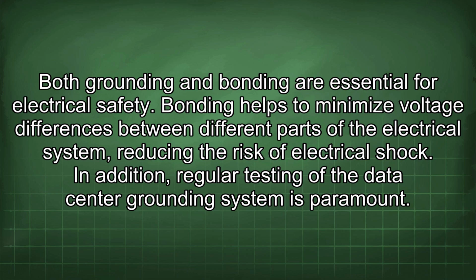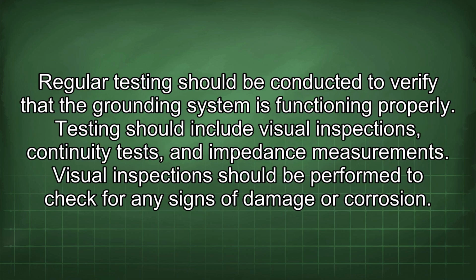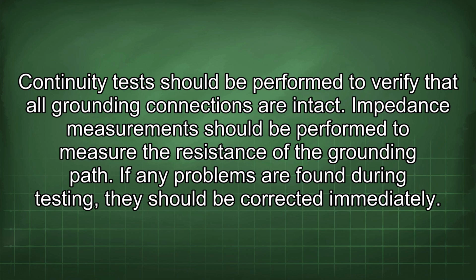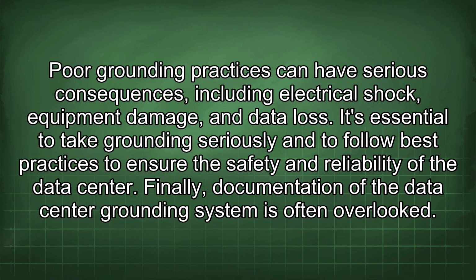In addition, regular testing of the data center grounding system is paramount. Regular testing should be conducted to verify that the grounding system is functioning properly. Testing should include visual inspections, continuity tests, and impedance measurements. Visual inspections should be performed to check for any signs of damage or corrosion. Continuity tests should be performed to verify that all grounding connections are intact. Impedance measurements should be performed to measure the resistance of the grounding path. If any problems are found during testing, they should be corrected immediately. Poor grounding practices can have serious consequences, including electrical shock, equipment damage, and data loss. It's essential to take grounding seriously and to follow best practices to ensure the safety and reliability of the data center.